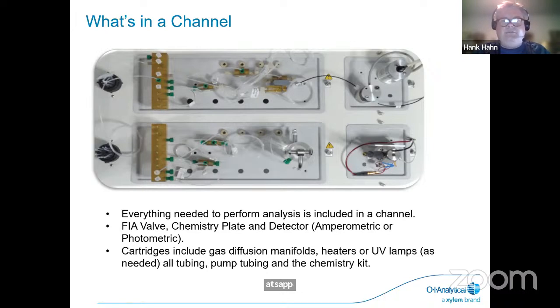So again, breakdown of a flow injection valve, the chemistry plate, and the specific detector for the chemistries that you do. And this one setup is, again, with ammonia, TKN, and then cyanide. Those two chemistries are extremely popular in the fact that these were developed and approved by the EPA back in 2012 to eliminate that kind of tedious distillation step.